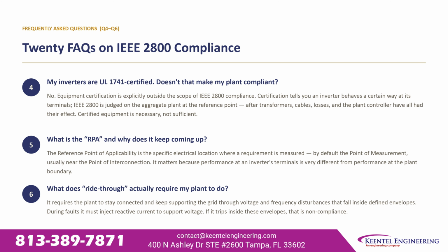What is the RPA, and why does it keep coming up? The reference point of applicability is the specific electrical location where a requirement is measured. By default, the point of measurement, usually near the point of interconnection. It matters because performance at an inverter's terminals is very different from performance at the plant boundary. What does ride-through actually require your plant to do? It requires the plant to stay connected and keep supporting the grid through voltage and frequency disturbances that fall inside defined envelopes. During faults, it must inject reactive current to support voltage. If it trips inside those envelopes, that's non-compliance.